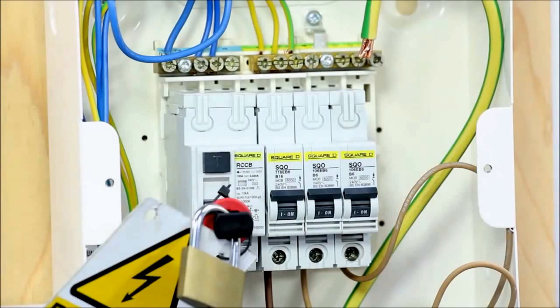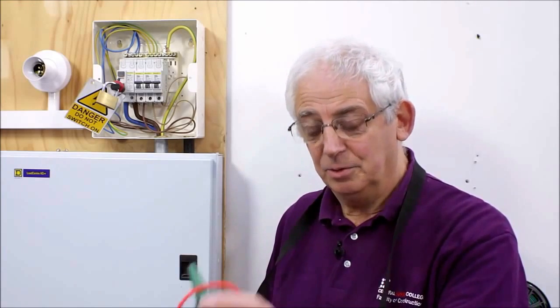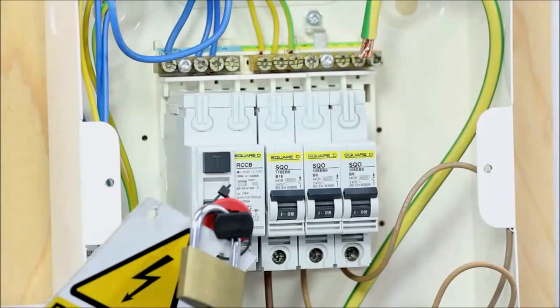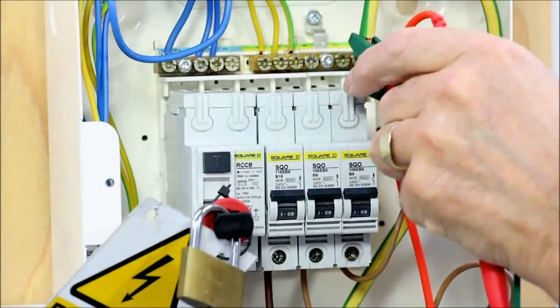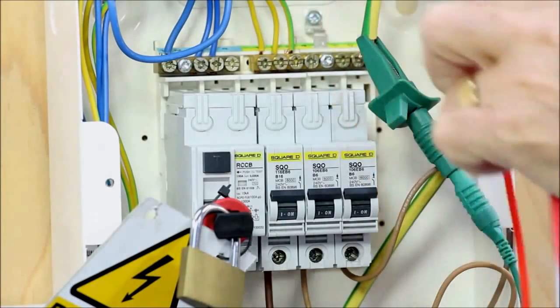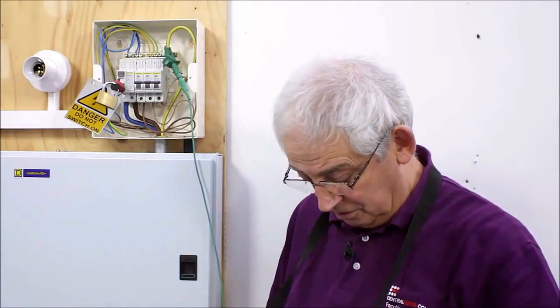What we're going to do now is a ZE test on a TT system. As you can see, I've already isolated the consumer unit, locked it off, and put the labels up so it's quite safe. I've disconnected the earthing conductor because when we take this measurement, we don't want any parallel paths included in the result. I have to use an earth fault loop impedance tester.